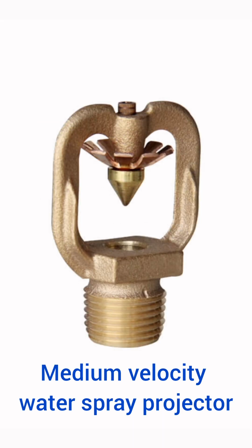The detectors are similar to those of sprinklers in construction, without deflectors, and are available in different temperature ratings. Two networks of pipeline will be there, one for projectors, which will be empty. The water will flow during the operation of the system.